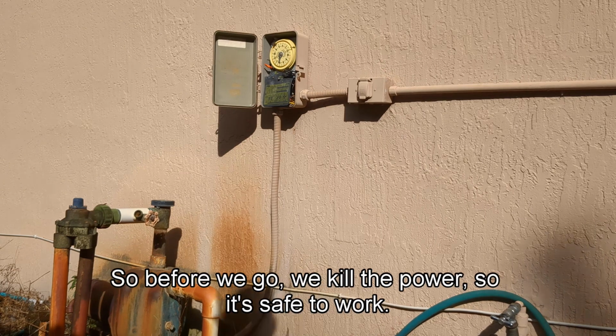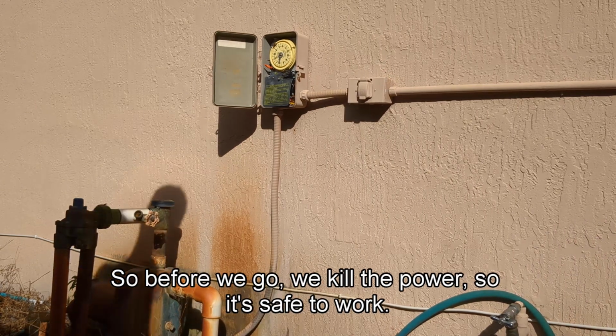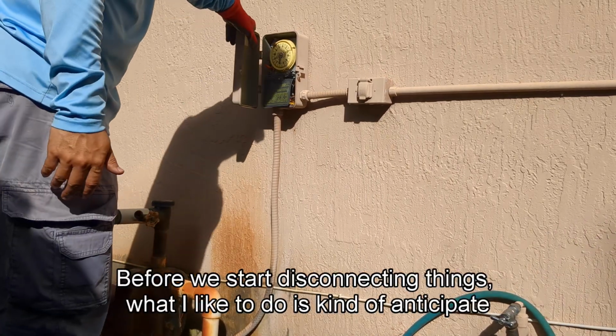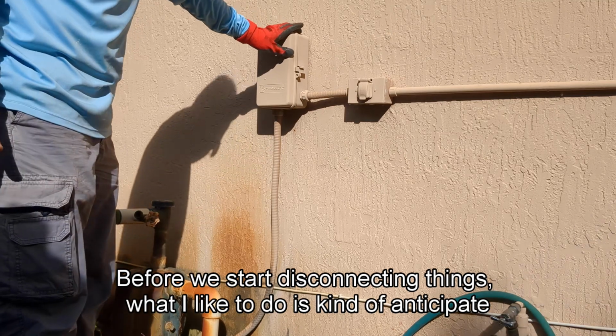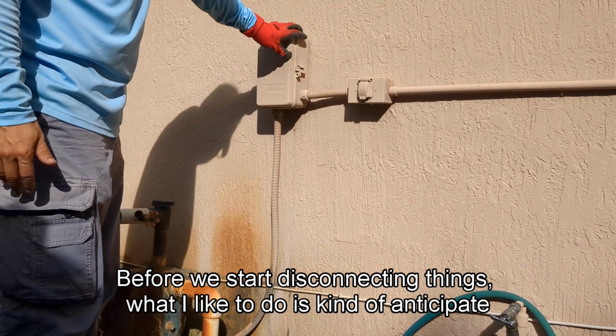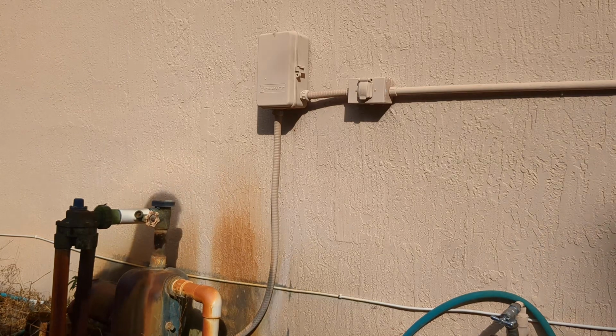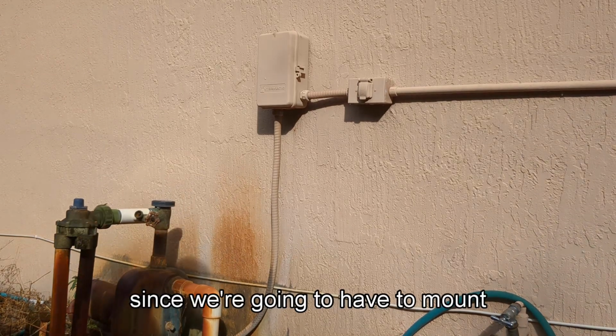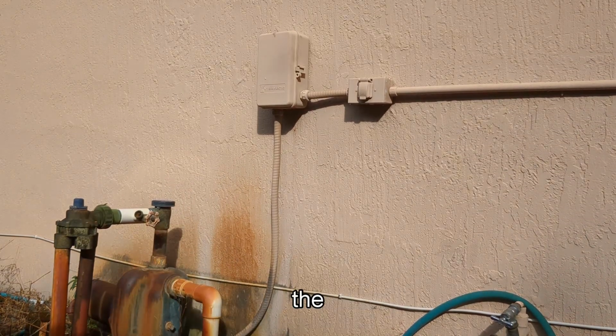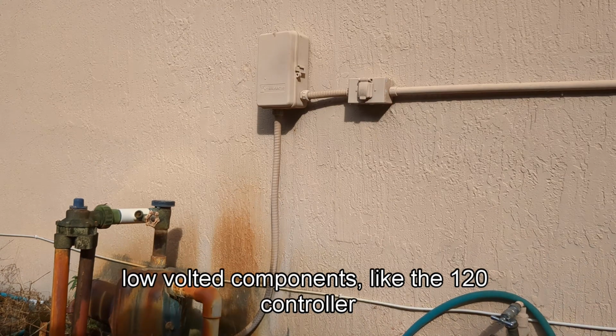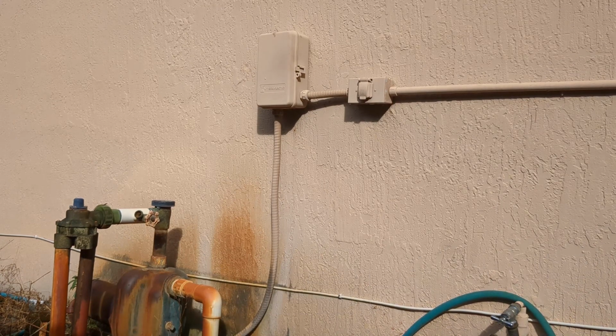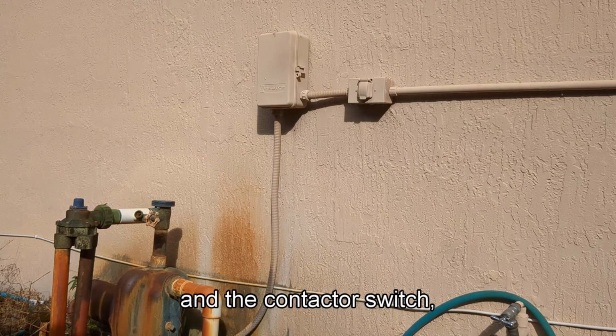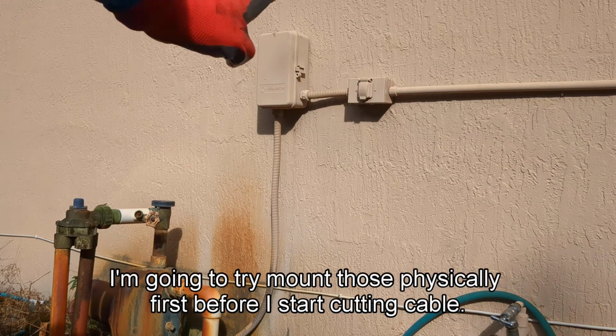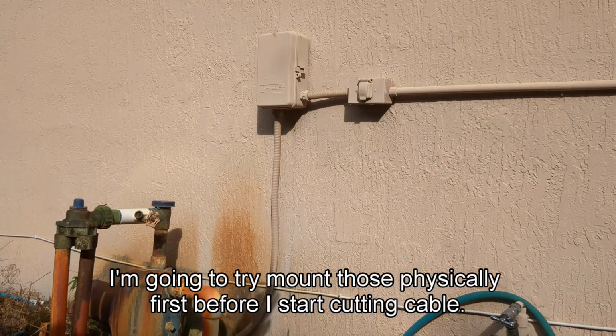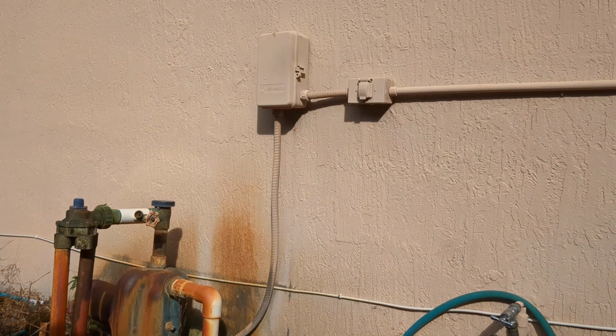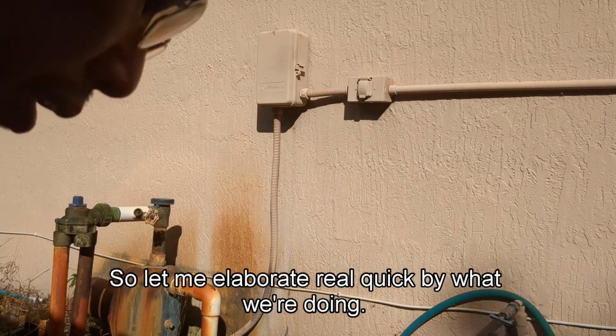So before we go, we killed the power, so it's safe to work. But before we start disconnecting things, what I like to do is anticipate what we're doing. So since we're going to have to mount the low voltage components like the 120 controller and the contactor switch, I'm going to try and mount those physically first before I start cutting cable. So let me elaborate real quick what we're doing.